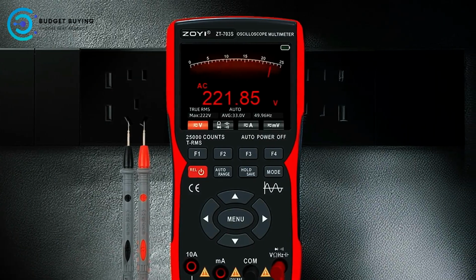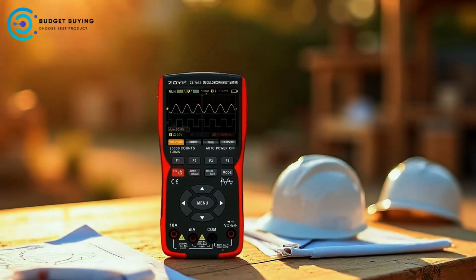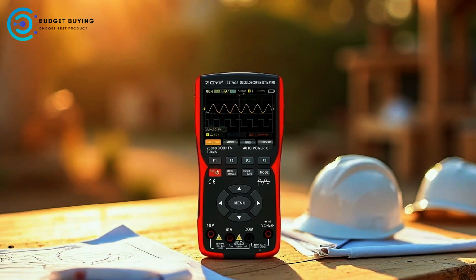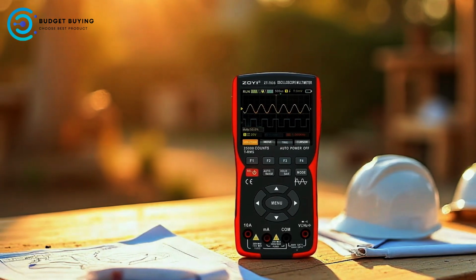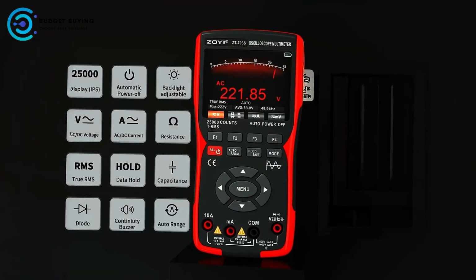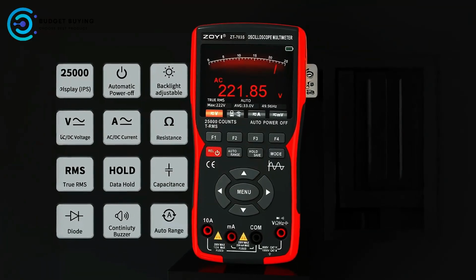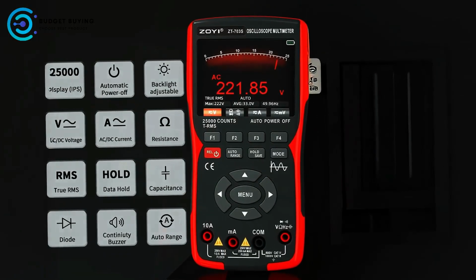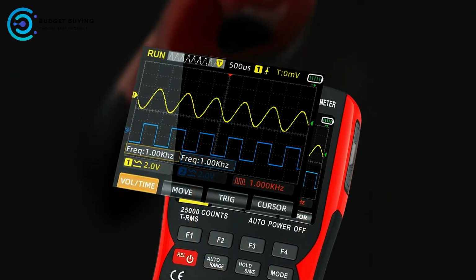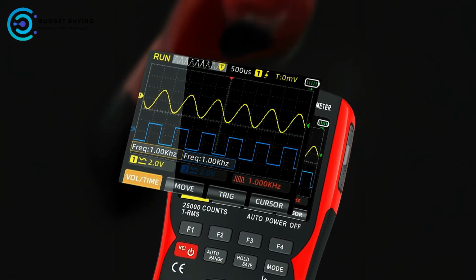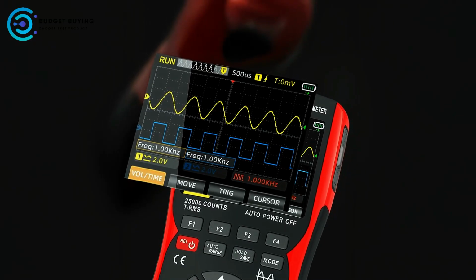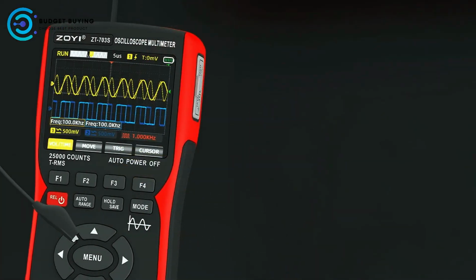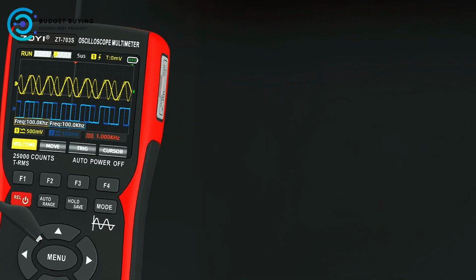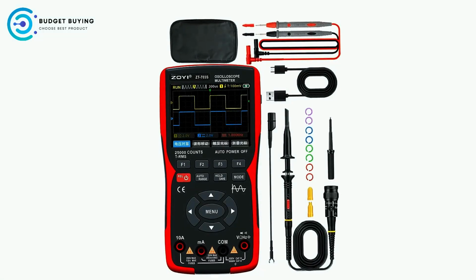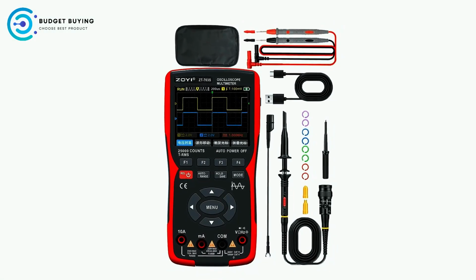The device supports arbitrary waveform voltage measurement and display, catering to a wide range of daily testing needs by accurately capturing various waveform types. One standout feature of the Zoyi ZT-703S is its one-key auto adjustment function. This function streamlines the process of waveform measurement by automatically fine-tuning settings for precise cursor-based parameter readings, thus saving time and minimizing manual adjustments. Additionally, the oscilloscope includes a persistence mode designed to capture signals more effectively.